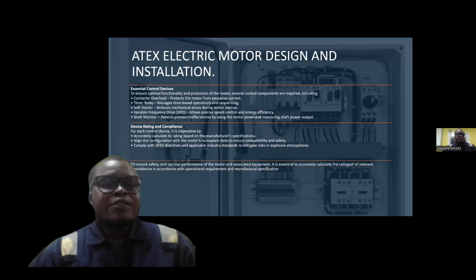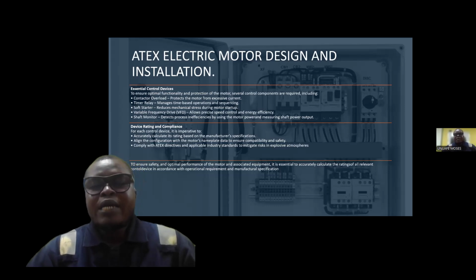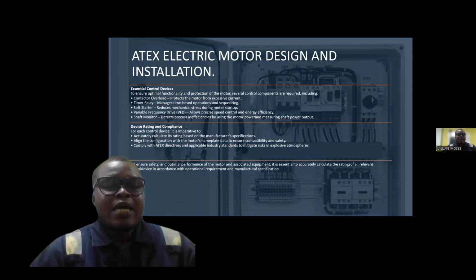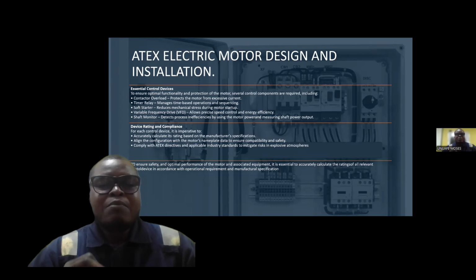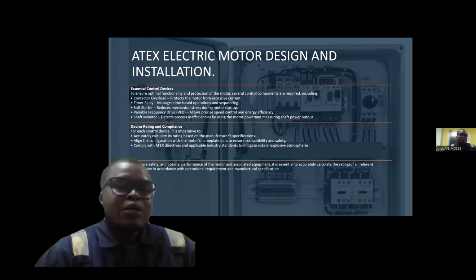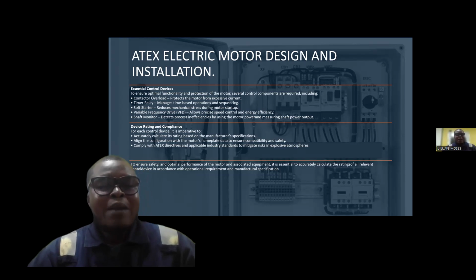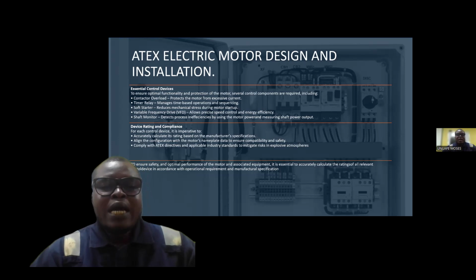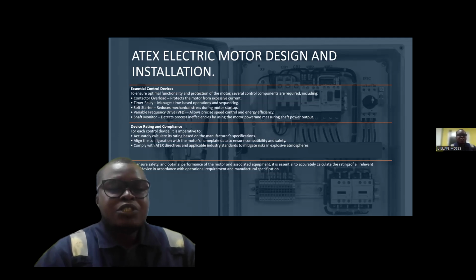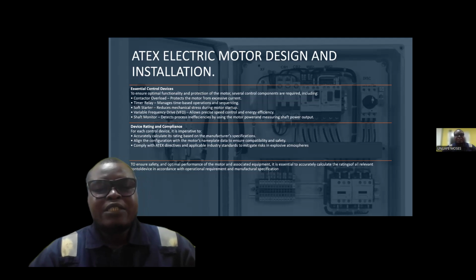These are the essential control devices to ensure optimal function and protection of the motor. Several control components are required, including, one, the contactors or overload, which protect the motor from excessive current. Another part is a time relay, which manages the time-based operation and sequences. Then we have the soft starter, which reduces the mechanical stress during motor startup. Then the variable frequency drive, which allows precise speed control and energy efficiency. Then the shaft monitor, which detects process inefficiencies by using the motor power to measure the shaft power output.